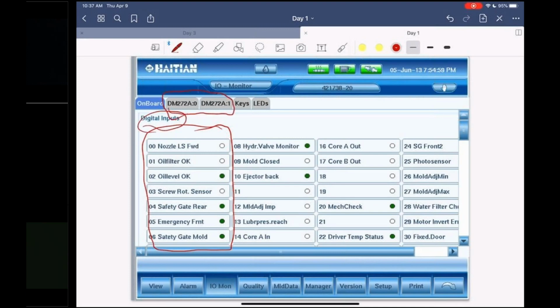If you have any expansion modules, there are 2 analog modules on this one. These are loaded at startup and are assigned by the software and are the actual values of where the locations are on the inputs and outputs. So if you scroll down here, I couldn't do it on this one because it's just a picture, but if you scroll down, you'll see all your outputs. Then you go to your analog pages and you can see all your analog signals, the keypad, your LEDs, all of that stuff. These are loaded again when the software loads at boot up. So these values or locations for your inputs and outputs can never be wrong. So if you have a problem trying to find something, let's say you couldn't see where your mold close signal is, you're looking for this guy. All you have to do is go to your input. So this mold close would be DI09.